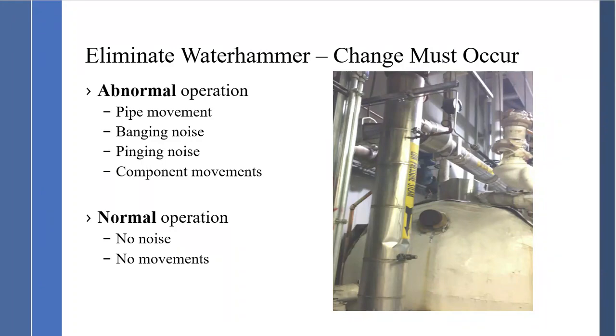Eliminate water hammer. Like I said, change must occur. Abnormal operation is pipe movement, banging noise, pinging noise, component movements. The normal operation should be no noise, no movements. So don't assume normal operation does have pipe movement, banging, pinging noise, and component movements. That's not normal. That's abnormal. The normal operation is when you walk in your facility, you hear no noise, no movement.